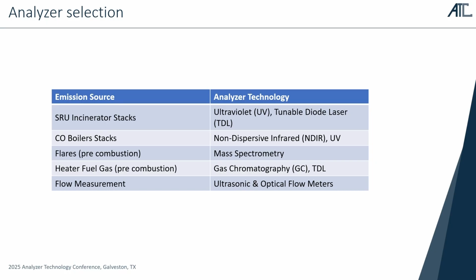Flare is more of a pre-combustion measurement, so now we're measuring the actual fuel composition. And for this case, various technologies were analyzed. Most arrived at either GC, gas chromatograph, or mass spectrometry, and most decided to go with mass spectrometry for this application, for the fast response time, as well as being able to multiplex and accurately measure the entire composition of the gas. And for heater fuel gas, that's another pre-combustion, some facilities chose to go with GC, and most chose to go with TDL because they only wanted the H2S composition, and the ones that wanted the more detailed composition of the gas went with the GC. And for flow gas, either ultrasonic or optical flow meters were used when the stream was very hot.